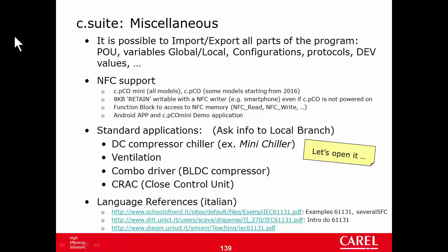The Ventilation application is meant to manage units with active and passive heat recovery and for compact area units. Combo Driver is somehow a reduced version of the first, but manages only the compressor part. It manages a BLDC compressor plus two on-off compressors, the electronic expansion valve driver, and the Power Plus. It also manages the chiller and heat pump unit, the envelope, the oil, and the source side, but it does not include temperature regulation. It receives the cooling demand from an analog input or from BMS, making it very interesting for testing the CAREL high-efficiency system and also for retrofit.